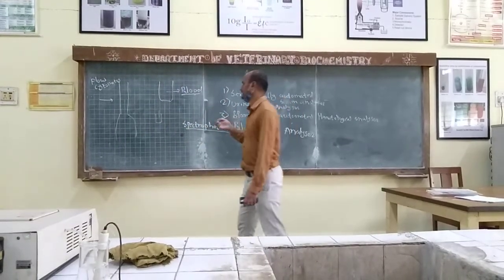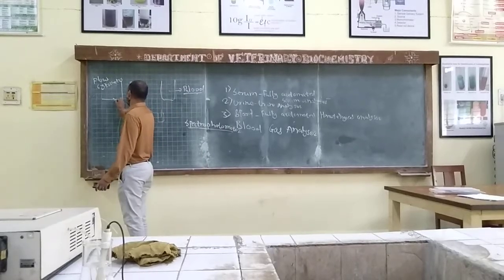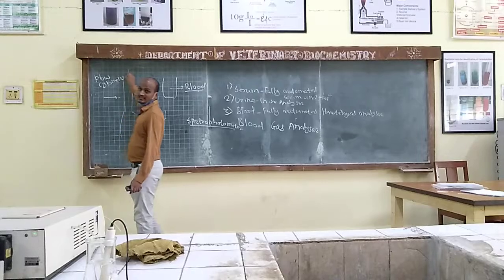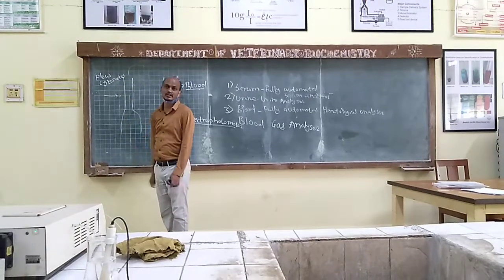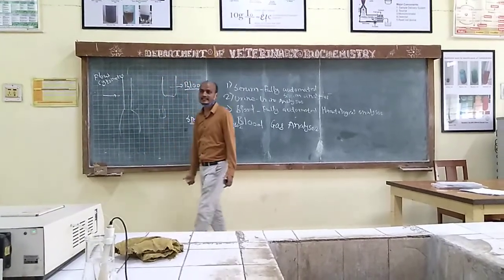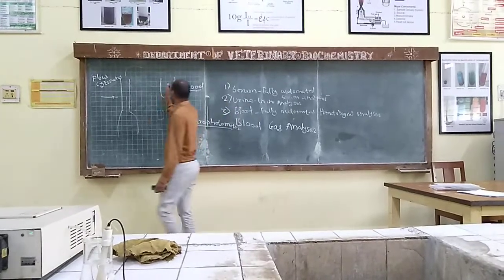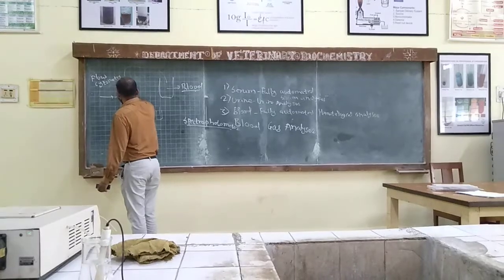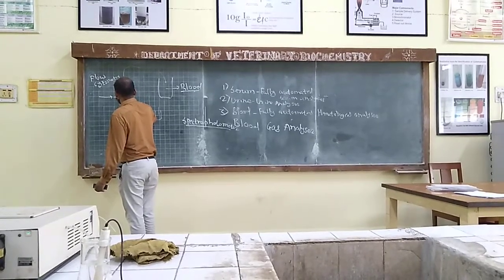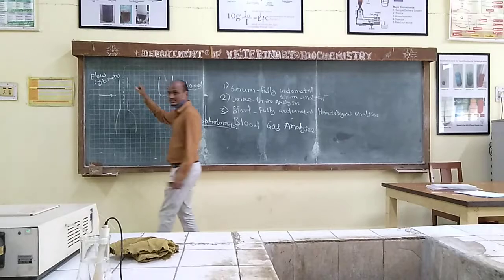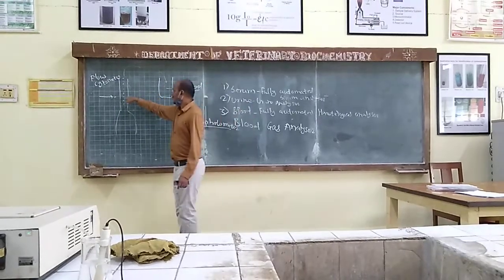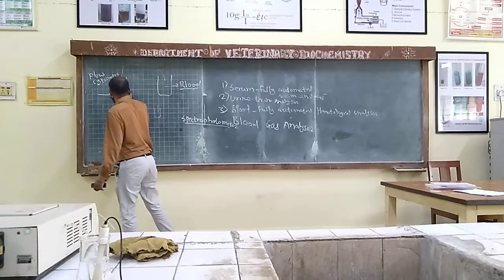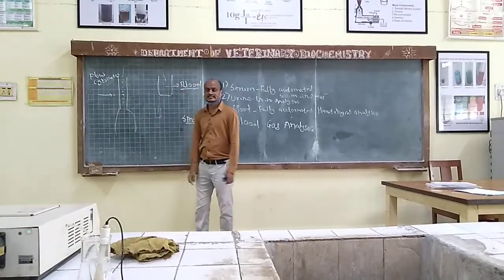But what is the principle of that blood sample? You are passing the laser here and you are adding a lot of diluent, so we say that this hematological analyzer requires a lot of diluent and a lot of reagent. Why does it require? Because we are feeding the blood to the sample and now this blood sample has to maintain single streams of cells. Okay, it has to pass in single streams. Now at a particular point when it is doing the analysis, a single cell should be there.